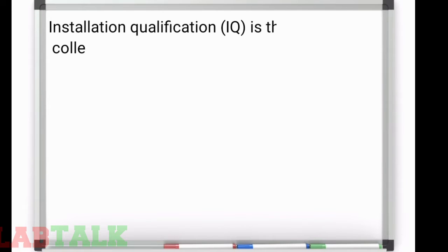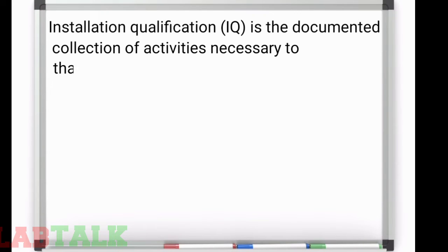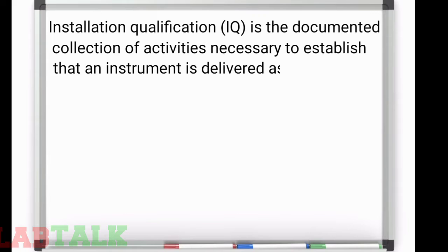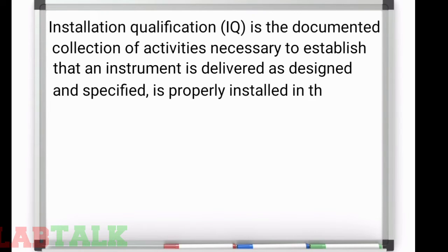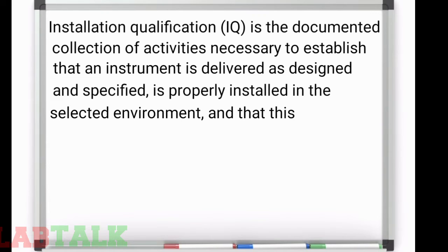Installation qualification is the documented collection of activities necessary to establish that an instrument is delivered as designed and specified and is properly installed in the selected environment, and that this environment is suitable for the instrument.